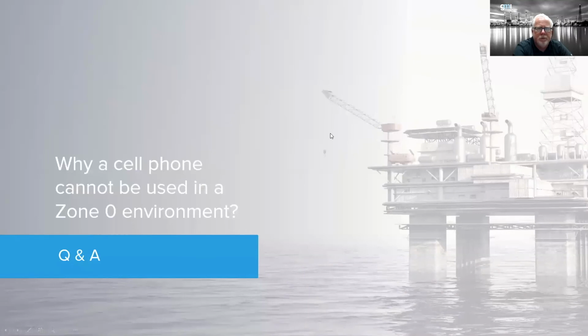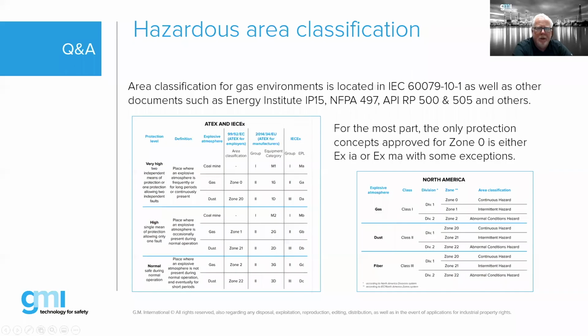Why can a cell phone not be used in a Zone 0 environment? That came from the sign up. I don't remember who posted this question. We have an answer here. Bob, do you want to take over this? Oh boy. Yeah, well, the protection concepts that are recognized for Zone 0 are either Ia, intrinsic safety with two fault tolerance, or Ma, encapsulation, again with fault tolerance. So there are cell phones that are certified Ib, and I've seen them, and they have single fault tolerance. I don't know why exactly you could not use a cell phone other than they are not certified for it.